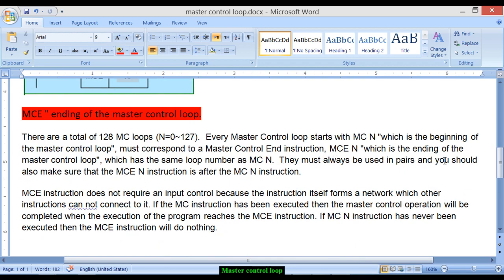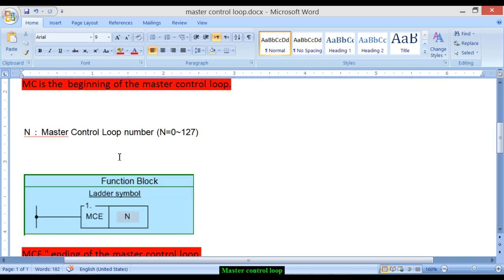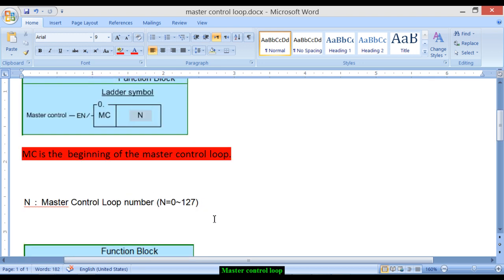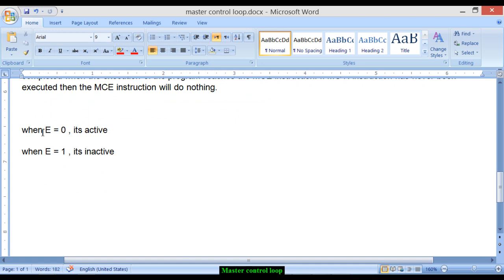MC and MCE must always be used in pairs. Make sure the MCE instruction comes after the MC instruction. In between, you can place other instructions like timers, counters, and anything else you want to use. The MCE instruction does not require any input control because the instruction itself forms a network that other instructions cannot connect to. If the MC instruction has been executed, the master control operation completes when execution reaches the MCE instruction.